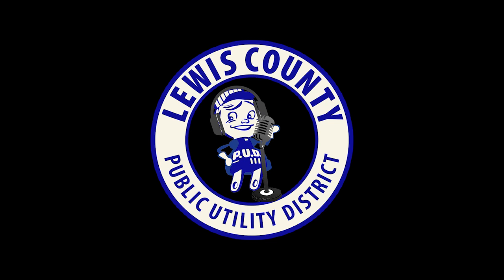For sure, I think there's a place for microgrids. First of all, a microgrid is having generation, like solar on people's houses or a battery or some other source of electricity, out away from the substation or even at a substation. If you have an outage and can disconnect that portion of the system, and it has its own generation and can supply power to it, it becomes a microgrid. Like I was talking about the radial feed out to a certain area, if that area goes down, we have a hydro source out there that can generate and supply power, even further up the line. Technically, when they separate from us, they're a microgrid because they're not connected into the greater grid. So we've been doing microgrids for a long time, we just didn't call it that back then.